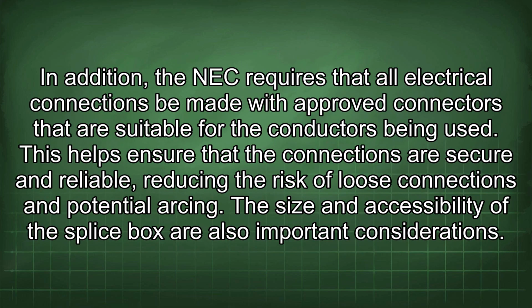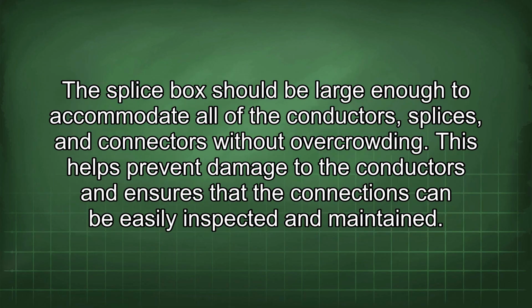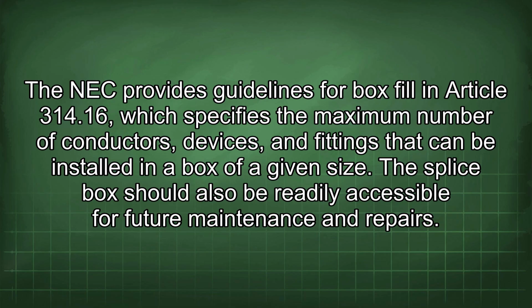In addition, the NEC requires that all electrical connections be made with approved connectors that are suitable for the conductors being used. This helps ensure that the connections are secure and reliable, reducing the risk of loose connections and potential arcing. The size and accessibility of the splice box are also important considerations. The splice box should be large enough to accommodate all of the conductors, splices, and connectors without overcrowding. This helps prevent damage to the conductors and ensures that the connections can be easily inspected and maintained. The NEC provides guidelines for box fill in Article 314.16, which specifies the maximum number of conductors, devices, and fittings that can be installed in a box of a given size. The splice box should also be readily accessible for future maintenance and repairs.